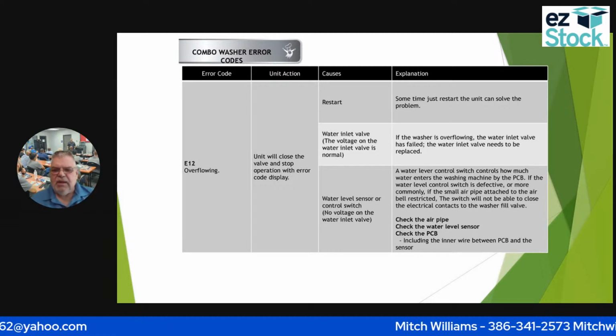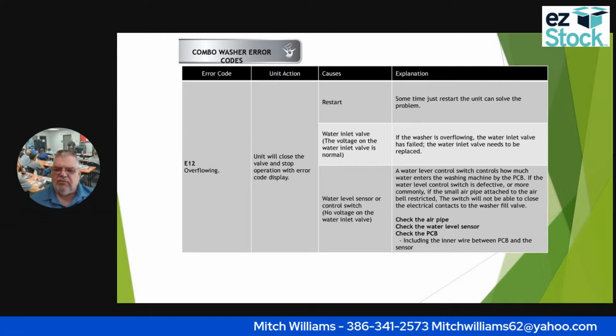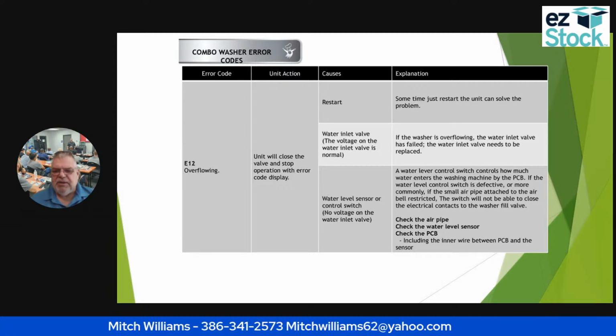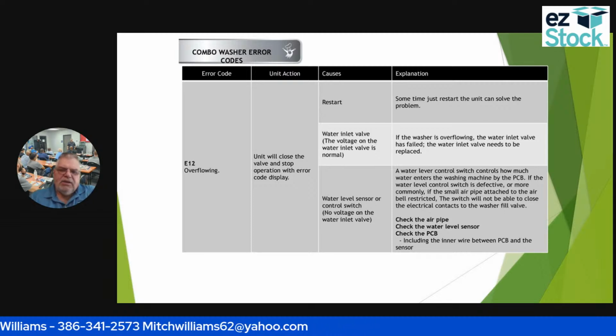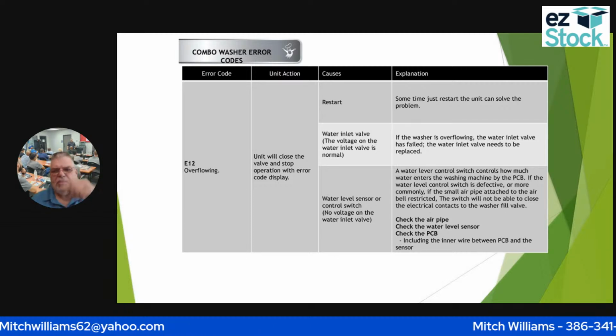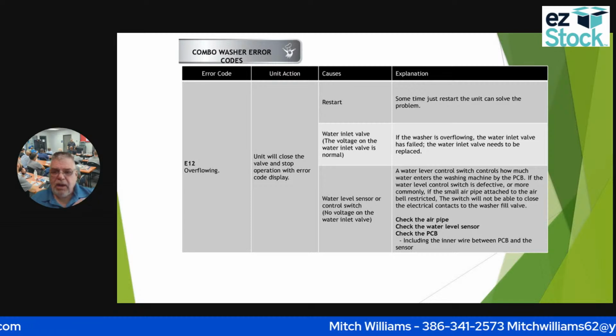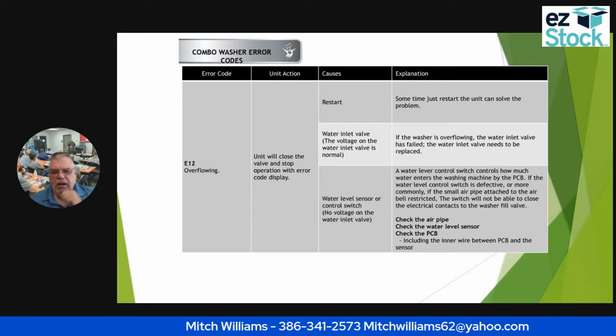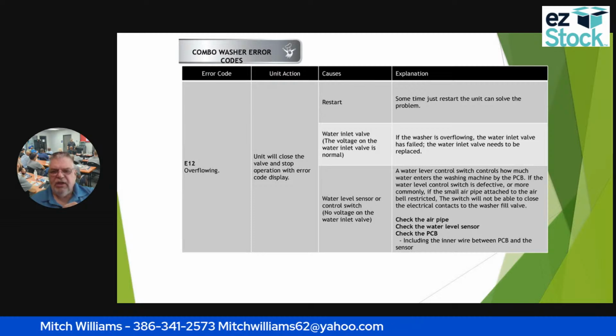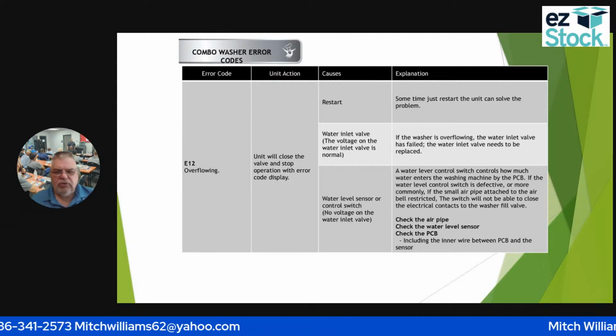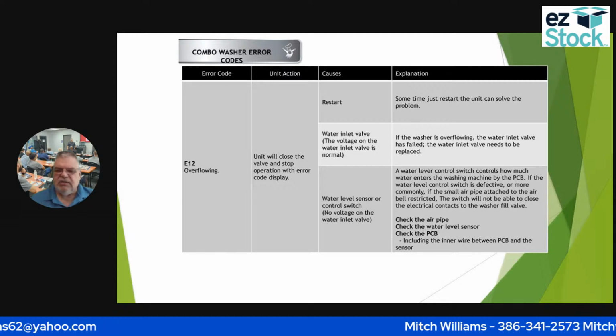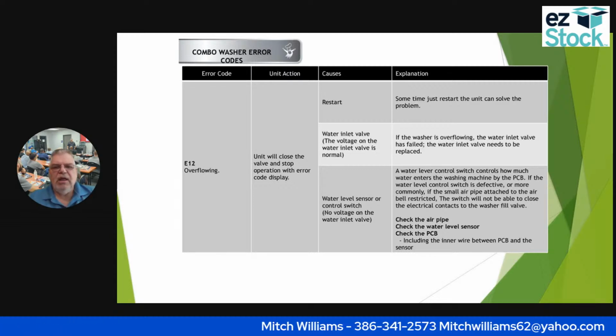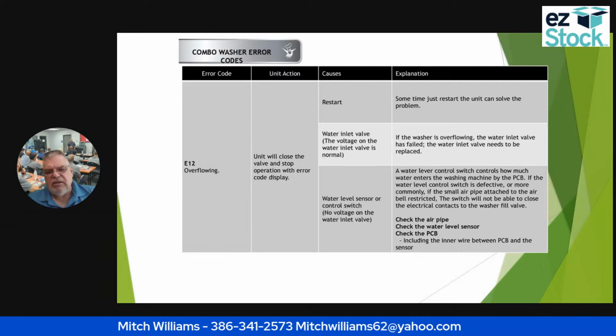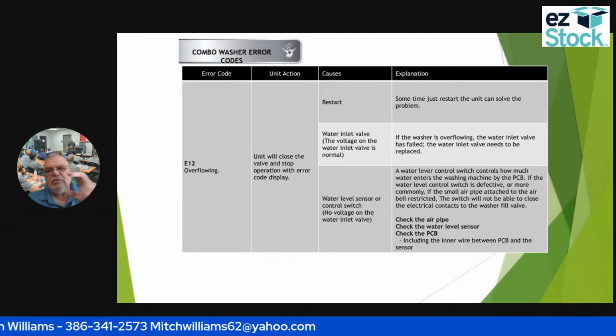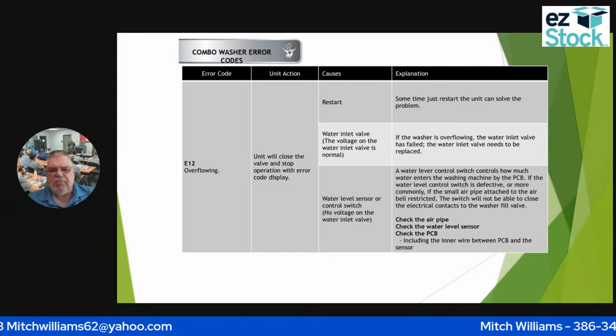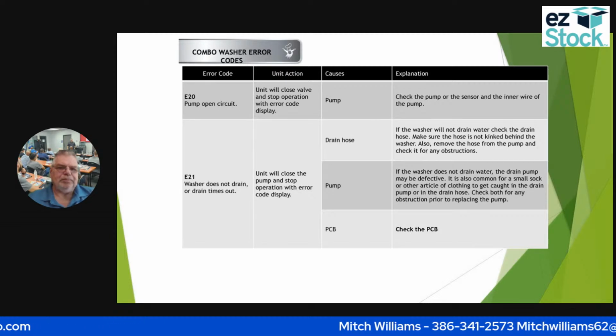I'm going to look at it. I'm going to check the air pipe. I'm going to check the water level sensor, and then I'm going to check the PCB. So that's all I'm going to do. I can do a visual check for the air pipe to see if the air pipe has any restriction in it. I can blow on the tube to see if it shuts it off. I can check my PCB, seeing what voltage I get through there, and if I'm not getting voltage telling the board to shut the water valve off, that's my problem, and I'm going to have to replace that PCB.